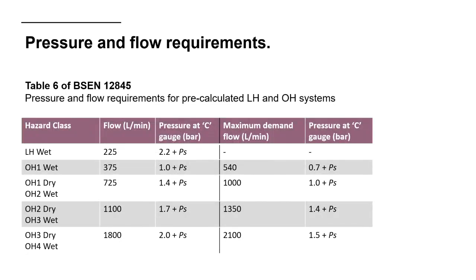So let's look at ordinary hazard group 3, wet. We're looking for a nominal flow of 1100 litres per minute, and we want to achieve that at 1.7 bar plus PS. Now, PS stands for pressure static. That is basically the height of the building. We need to allow for the water to travel up the pipe to the heads on the top floor, so we need to add that on to our pressure requirements. The taller the building, the more pressure we need from our town main in order for it to still be sufficient. Makes sense? The higher the building, the more that water needs to travel up the pipe. As it goes up, it loses pressure due to gravitational effects.